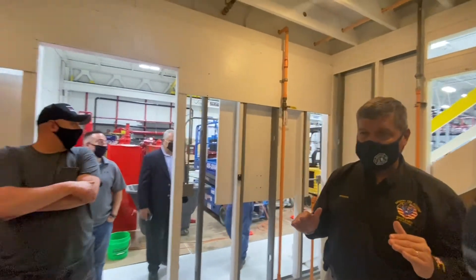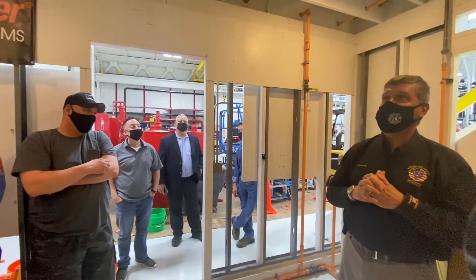Remember, you're not doing the design — you're just reviewing to make sure that's what they did. You're looking at the heads, checking that we have hangers. We have some hangers on here. This looks okay in here. Let's go over to that room for just a minute.